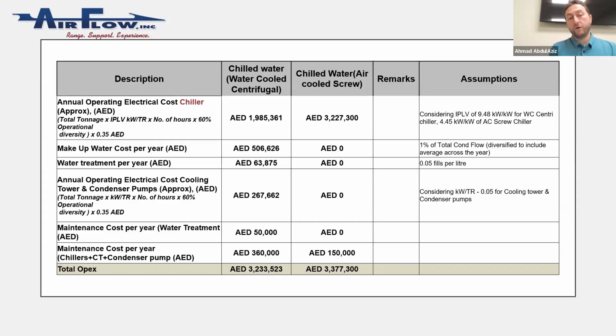Now you have your annual operating cost. Now you have to consider part load, because as per ASHRAE, you are running 1% at your full load, 99% at your part load. So if you do some analysis, you do that calculation based on the kilowatt rate in your area, then you will get 1.9 million dirhams for water cooled, but almost double that, 3.2 million, for air cooled, because it's less efficient than a water cooled system.